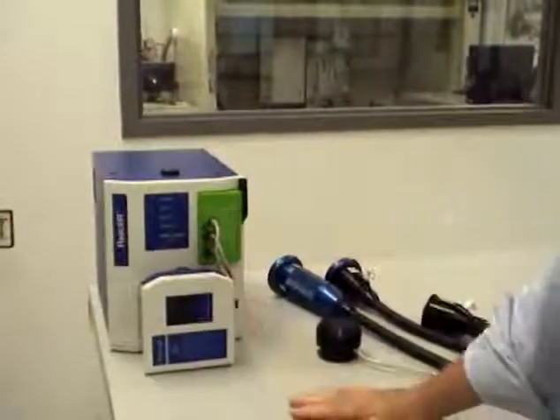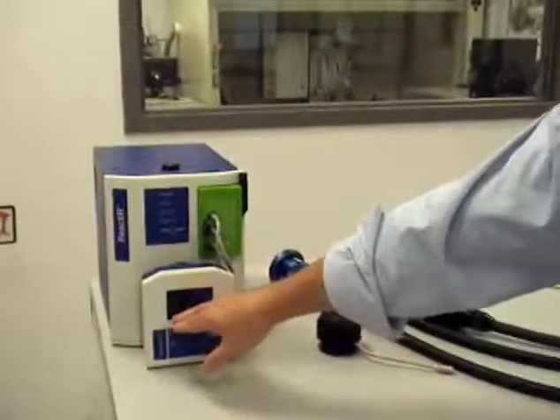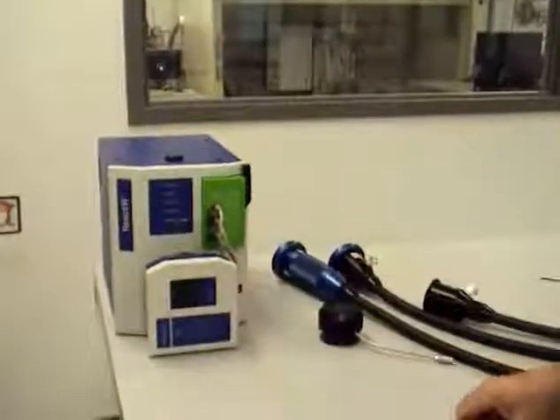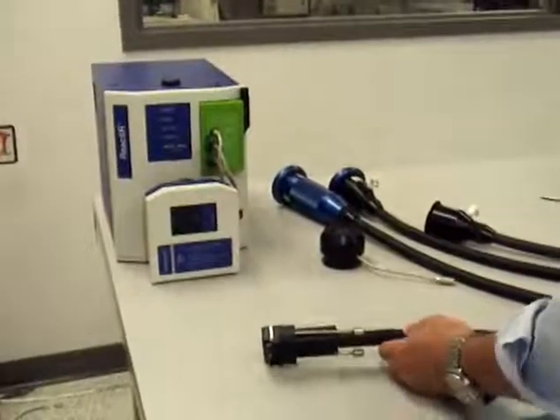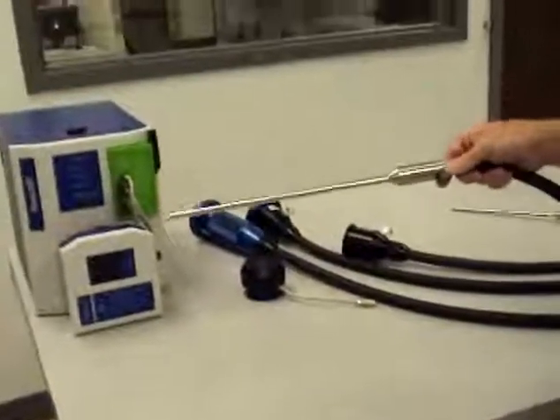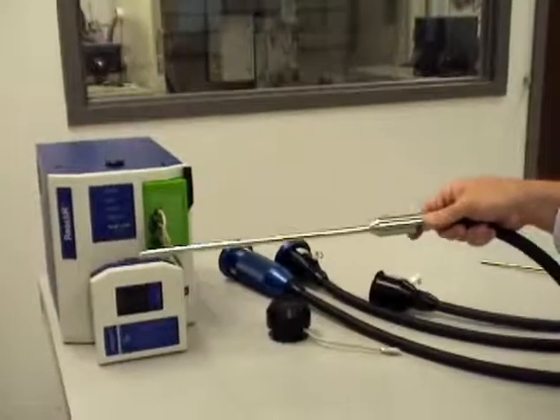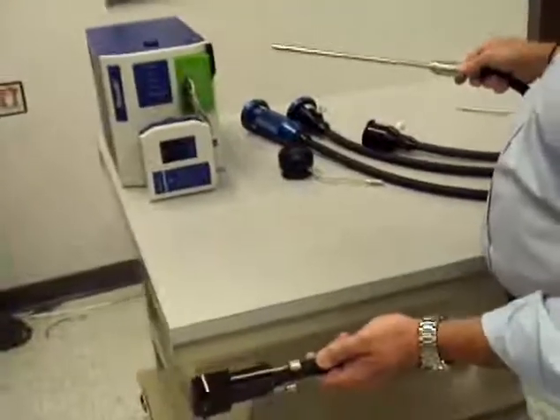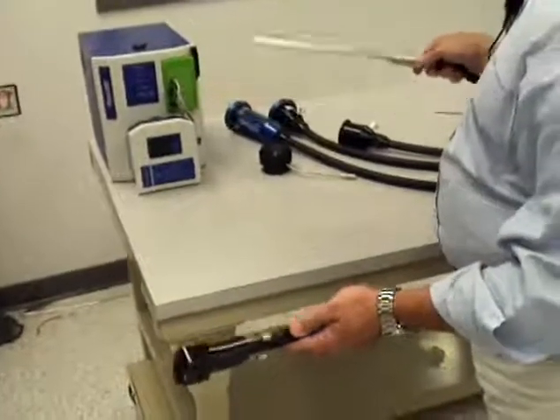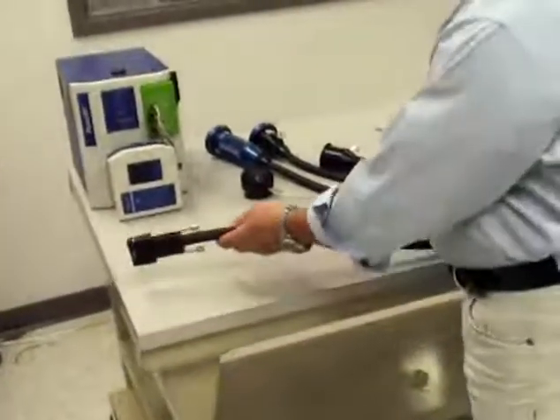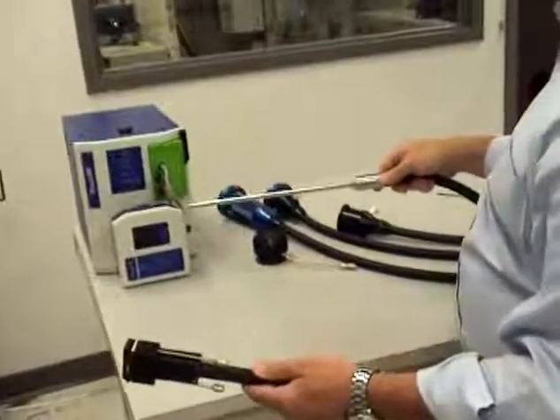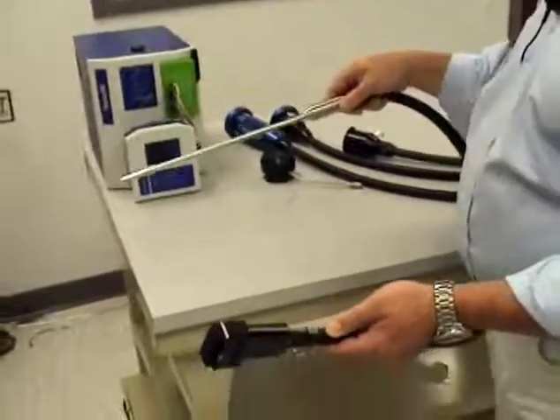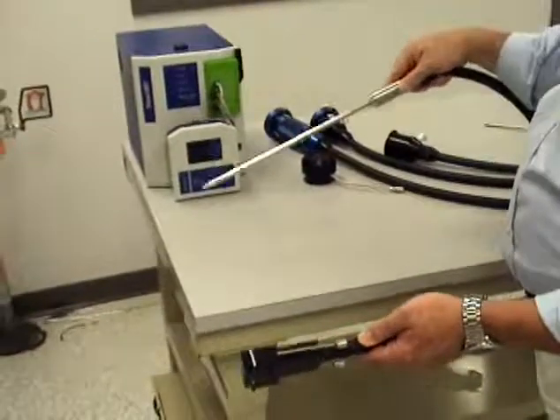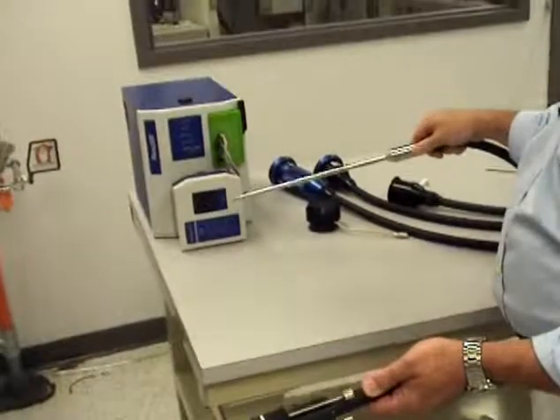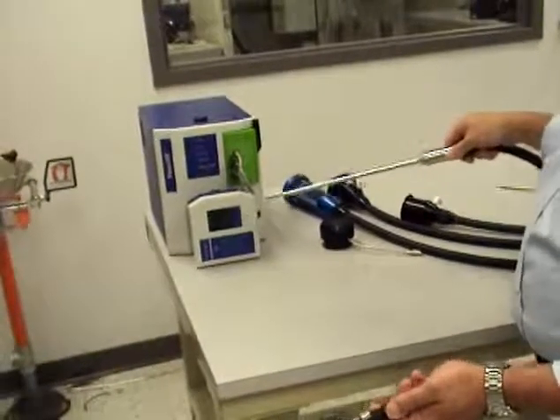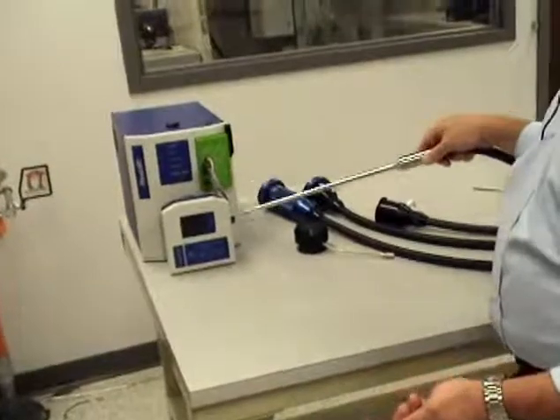The way that works is we can collect information from two different sampling technologies. They can be similar sampling technologies—it could be an EasyMax with two reactors, for example, where you're collecting information from two similar reactions at one time. Or it could be something completely different, where you want to collect information from a liquid phase and from a gas phase, or the headspace of a reaction. So you have a liquid sensor probe like this, an insertion probe, and then a gas cell on the other, and it simply moves from one to the other continuously.